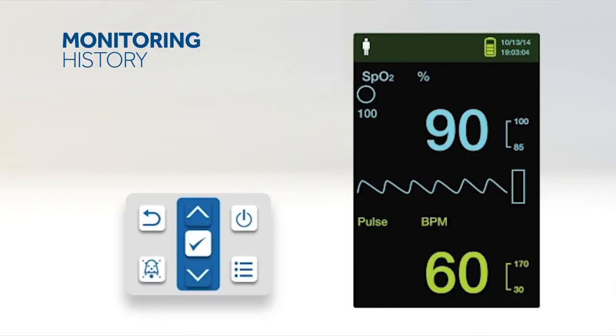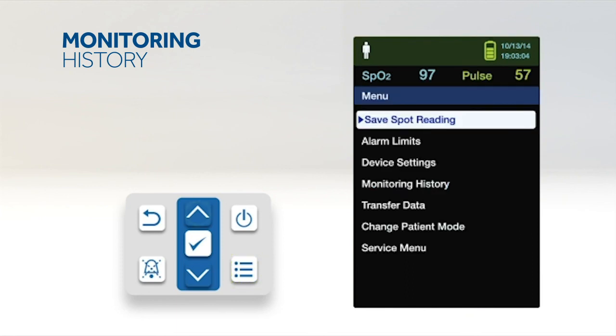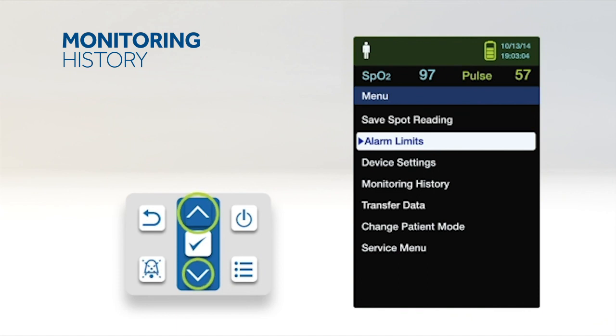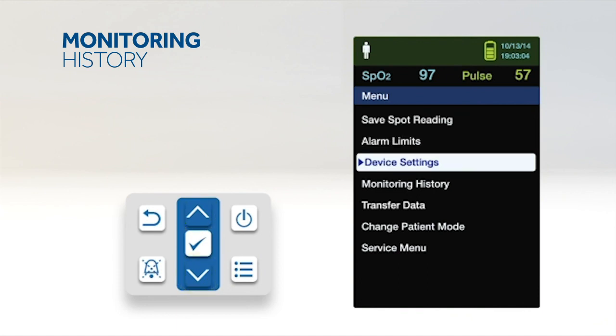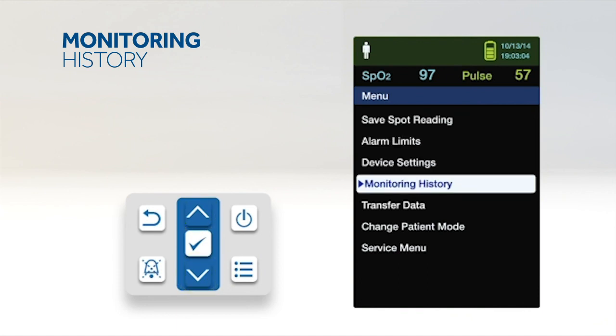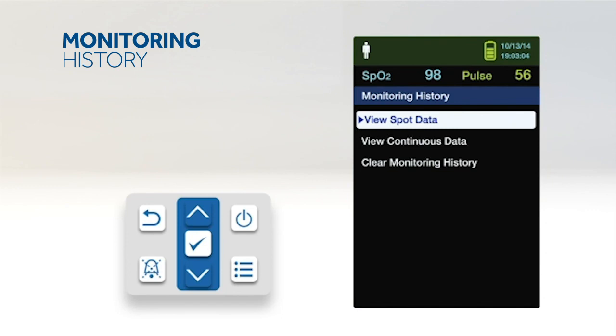The PM10N presents trend information in tabular format. The newest data values appear at the top. To review monitoring history, press the Menu button. Press the up or down button to highlight the Monitoring History menu, then press the OK button to select the menu. From the Monitoring History menu, select View Spot Data or View Continuous Data.